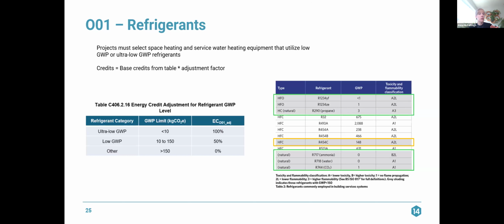So if you're using the ultra low GWP, you are going to achieve 100% of the credits available, which in the Model Low Energy Carbon Code, there are about 1 or 2 credits available based on climate zone and occupancy type for this credit. You're not getting 50 credits for this. If you select a low GWP refrigerant, then you achieve 50% of the credit, and if you have a greater than 150 kilograms of CO2 GWP limit, then you will not achieve any credits.